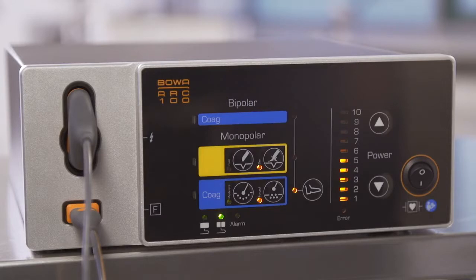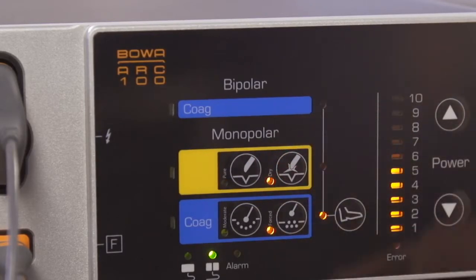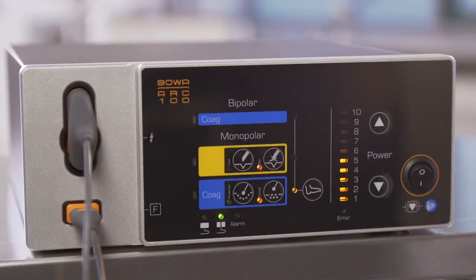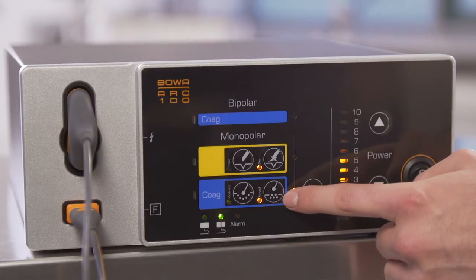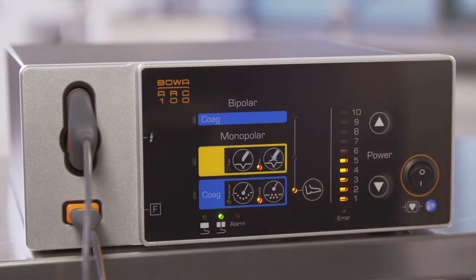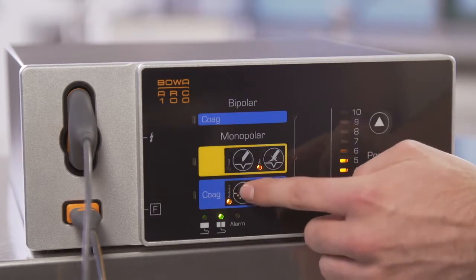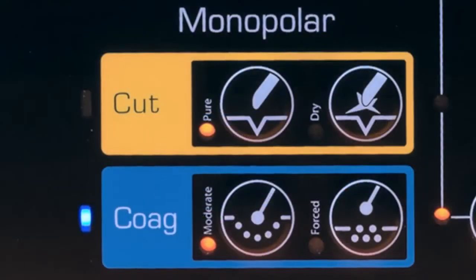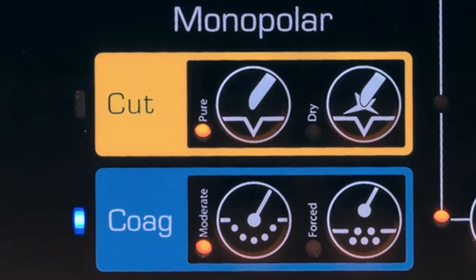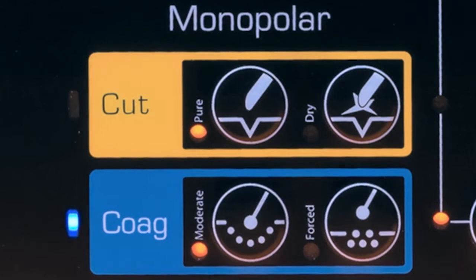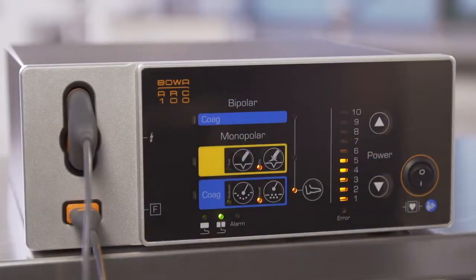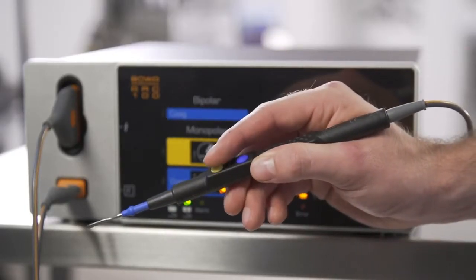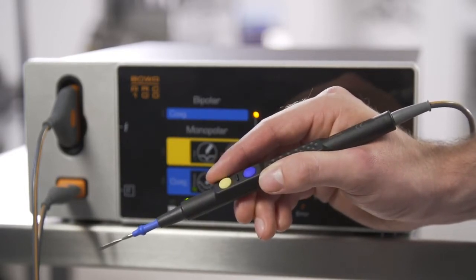Monopolar cutting is used for electrosurgical separation of tissue when using monopolar cutting instruments with electrodes. 2 modes are available: conventional cutting and dry cutting. 2 monopolar coagulation modes are available: moderate and forced coagulation. Moderate coagulation is used in the case of contact coagulation to stem hemorrhagic oozing, hemostasis in larger tissue areas, and for coagulation over small areas. Forced coagulation is coagulation using a semi-contact procedure. It is an effective procedure for rapid hemostasis close to the surface and for coagulation over larger areas.